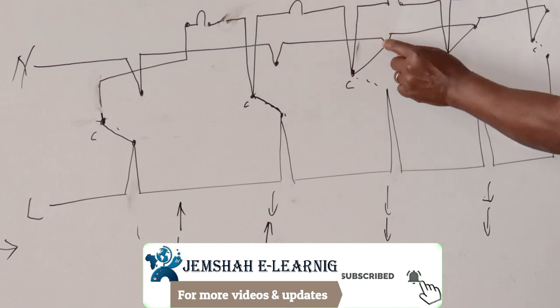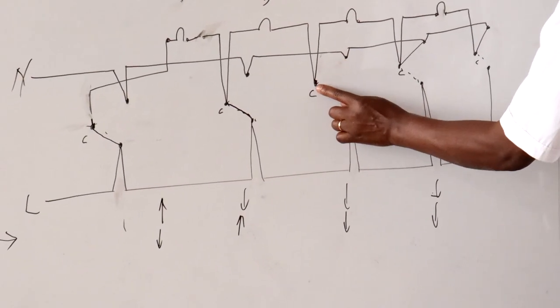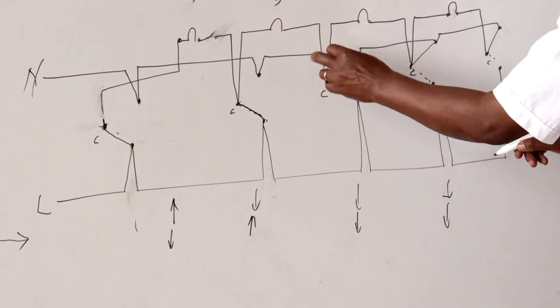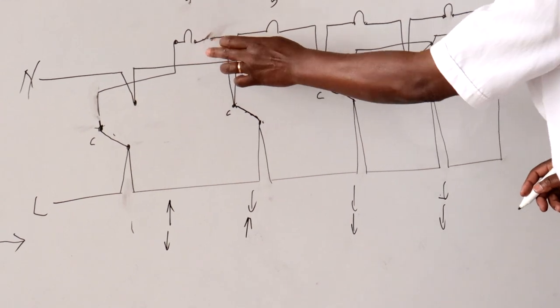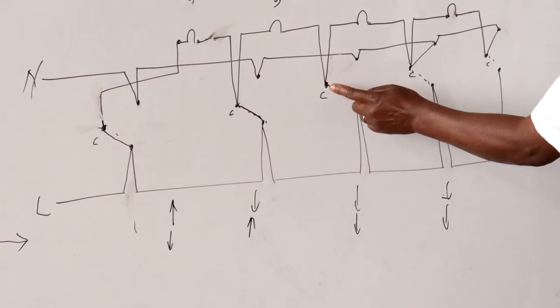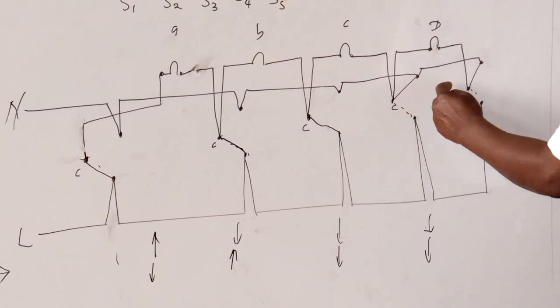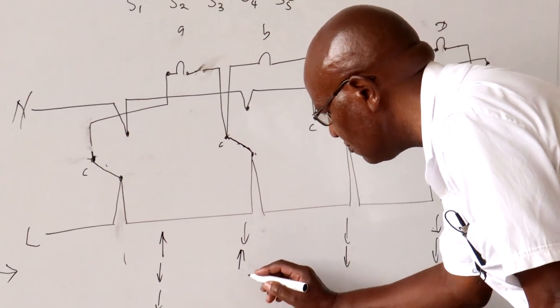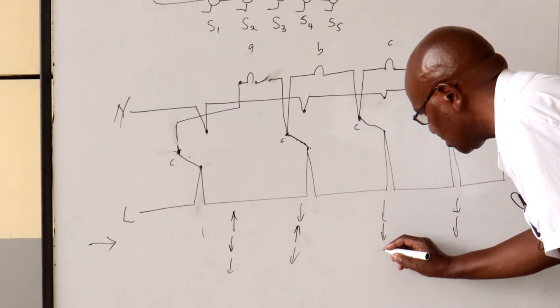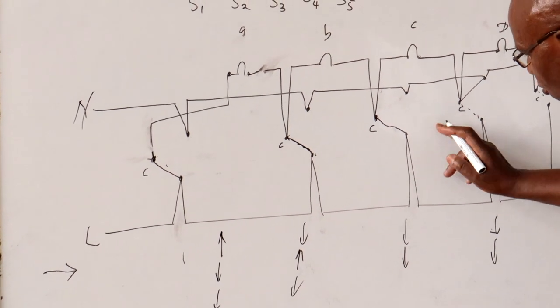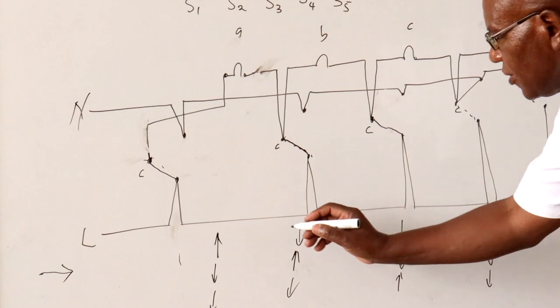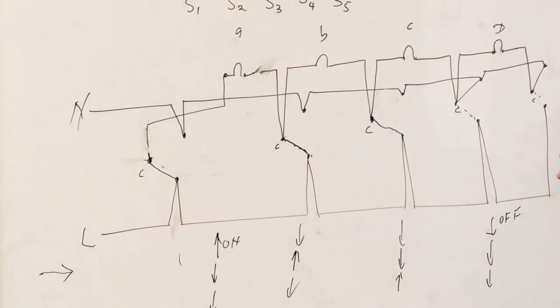Then I move to the next switching position. The path for lamp B to the neutral was through that switching connection. When I flip this one over, lamp B automatically goes off. The live passes through to the common terminal, and lamp C comes on through its connection back to the neutral. So lamp C is the one that is switched on at this stage.